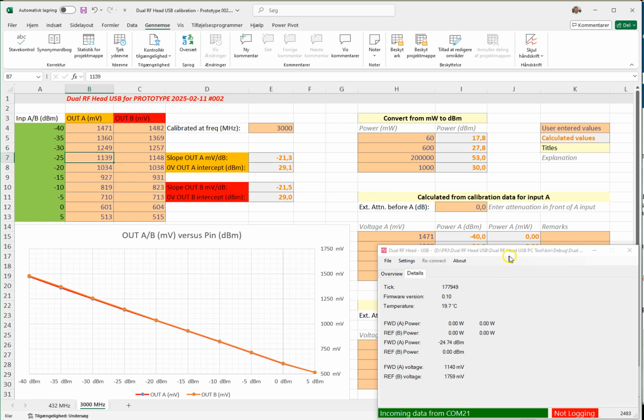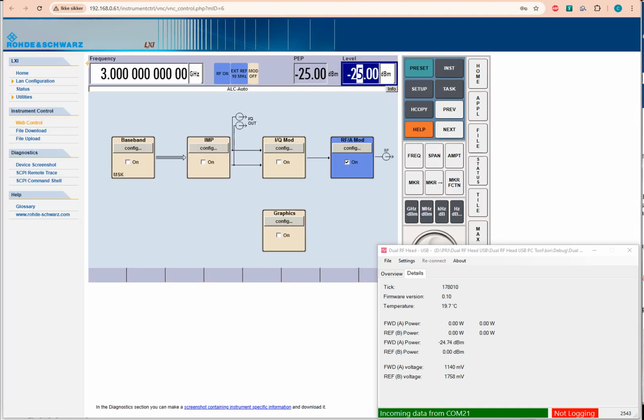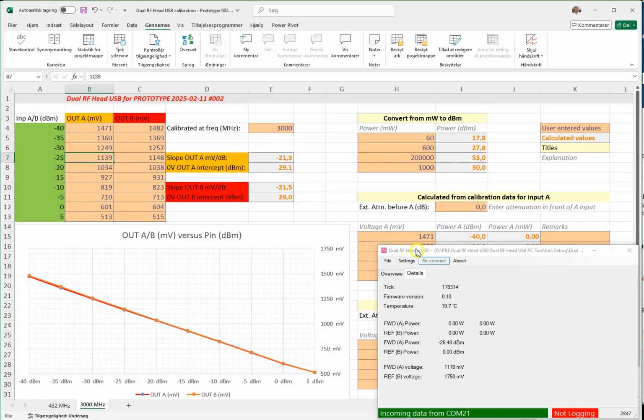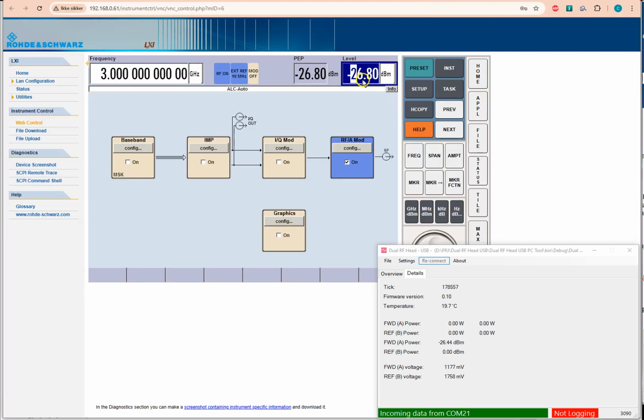And if we go to, let me type in some arbitrary number, -26.8. Okay. -26.8 dBm, that gives us 1178. I go to the spreadsheet and I go here and I say 1178. Okay, it shows me that based on the calibration values and this slope and this intercept point, I should see -26.2 dBm. I typed -26.8, so it's a difference of about 0.6, and there's no guarantee that my generator is accurate within 0.1 dB or something like that. So there will be differences.